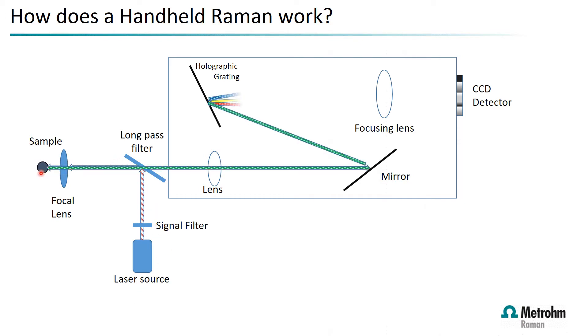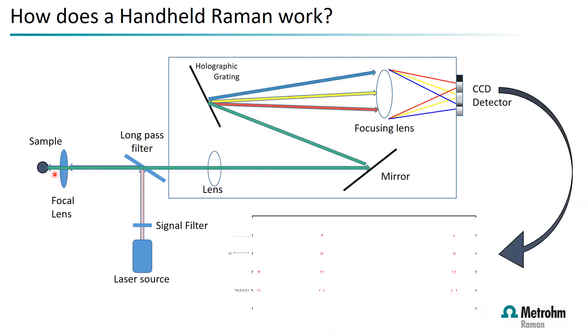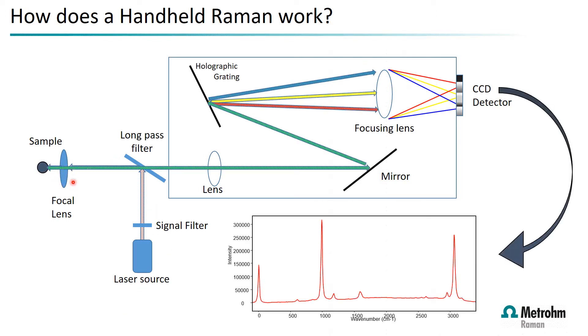How does a handheld Raman work? Essentially, we take a high-intensity laser source and focus the light onto a sample through a focal lens — we have a selection of these depending on the type of sample. The Raman shift is collected by filtering out the single wavelength from the laser and collecting only the Raman-shifted signal back into the device.